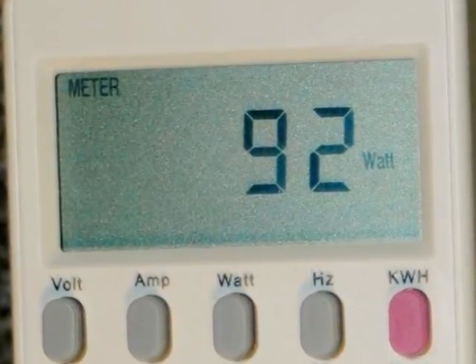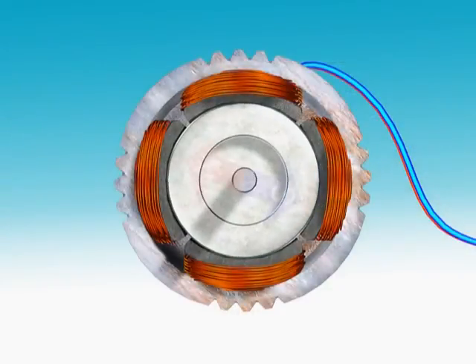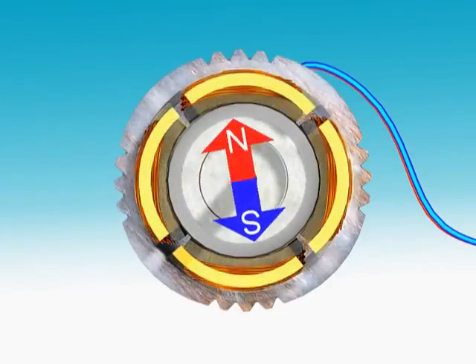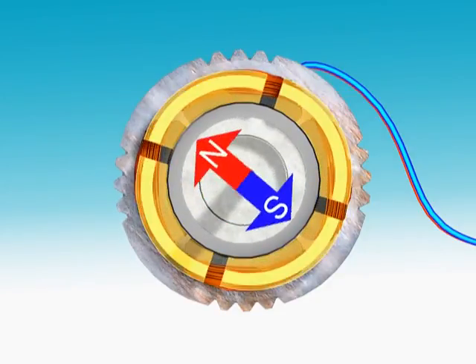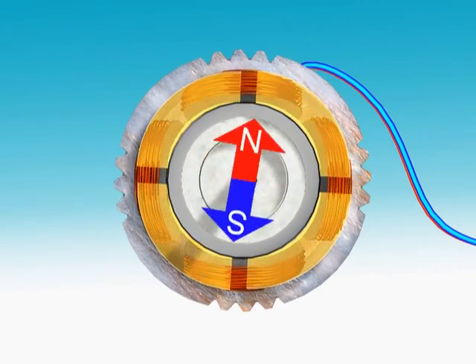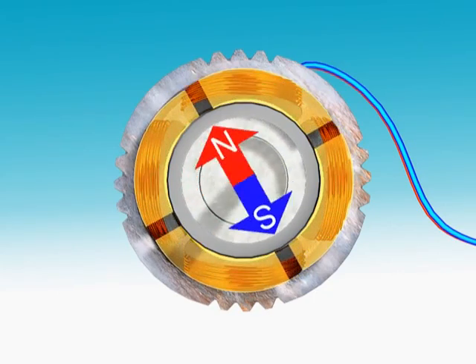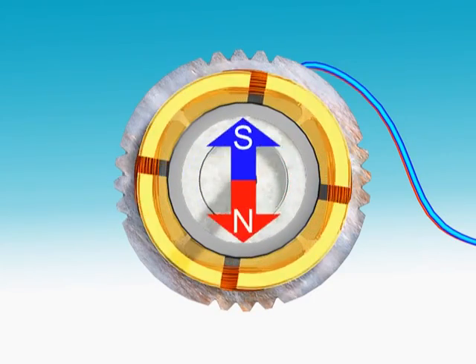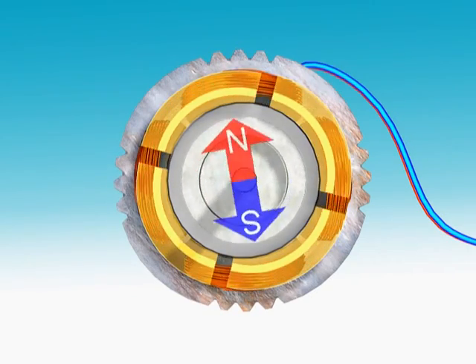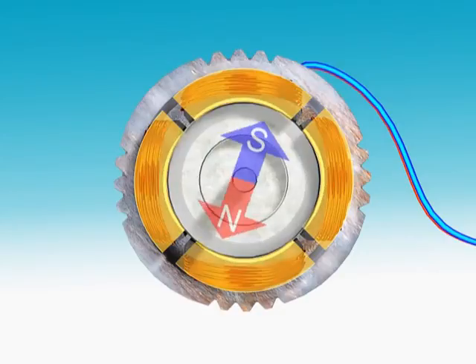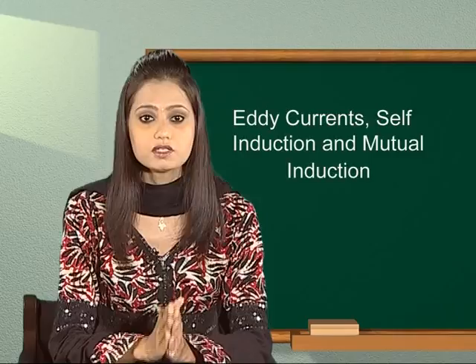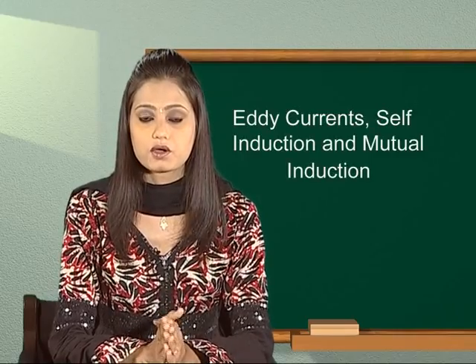In energy meters, the armature coil carries a metallic aluminum disc which rotates between the poles of a pair of permanent horseshoe magnets. As the armature rotates, the current induced in the disc tends to oppose the motion of the armature coil. Due to this braking effect, the deflection is proportional to the energy consumed.